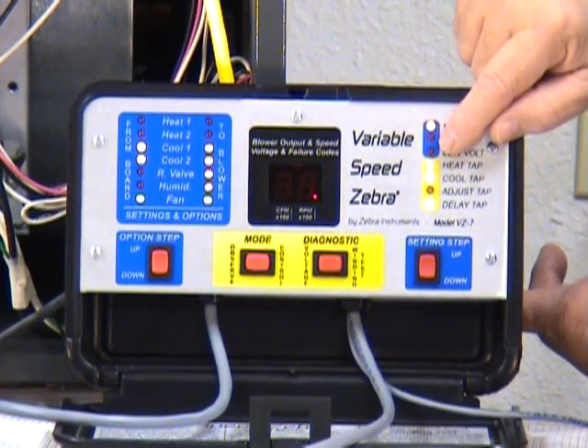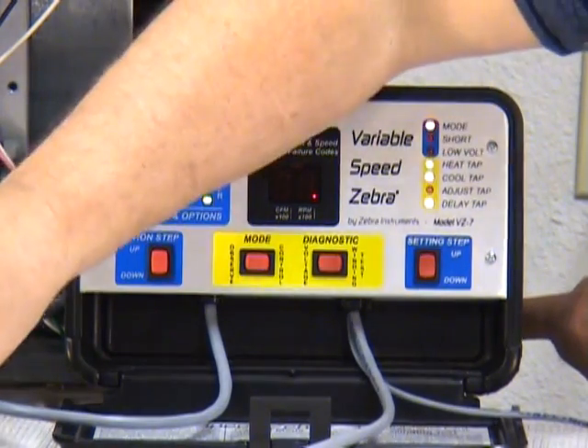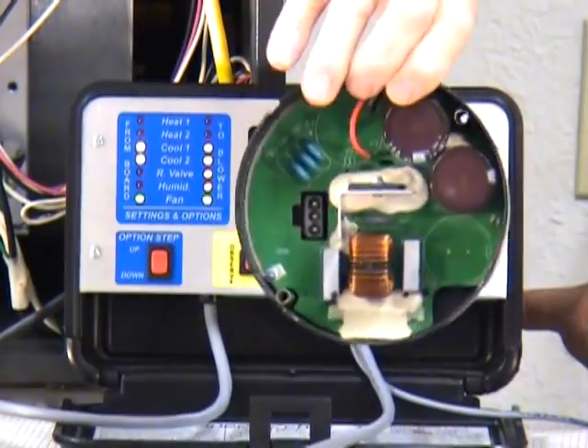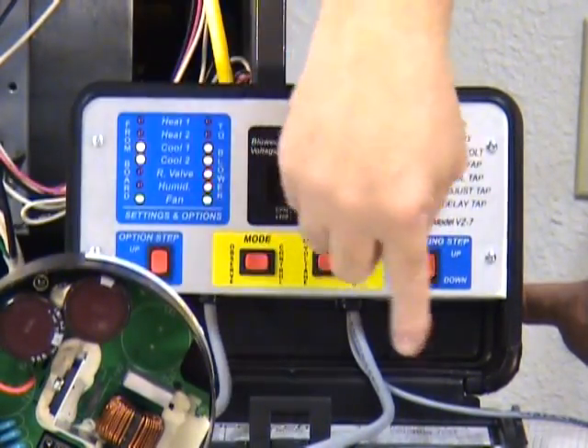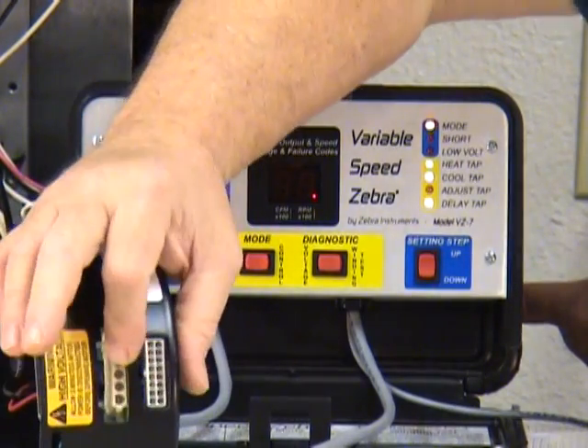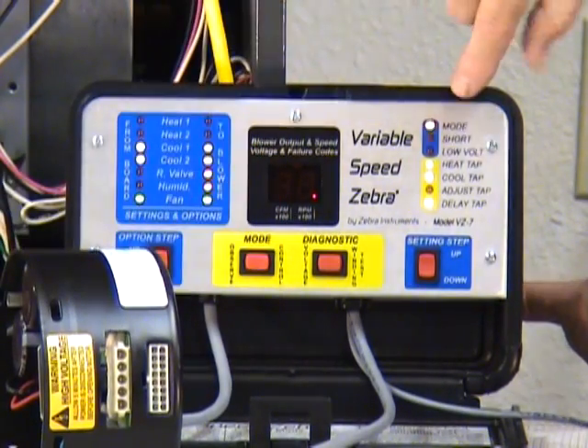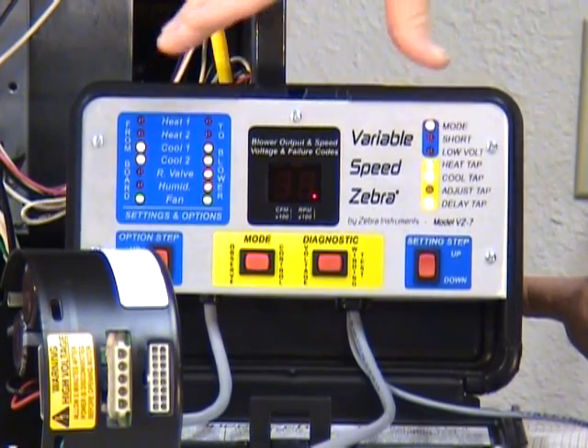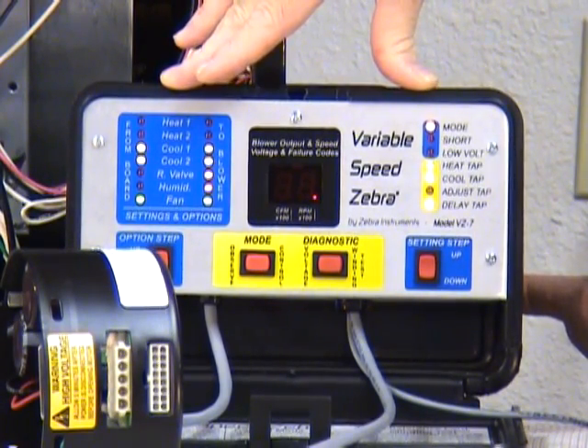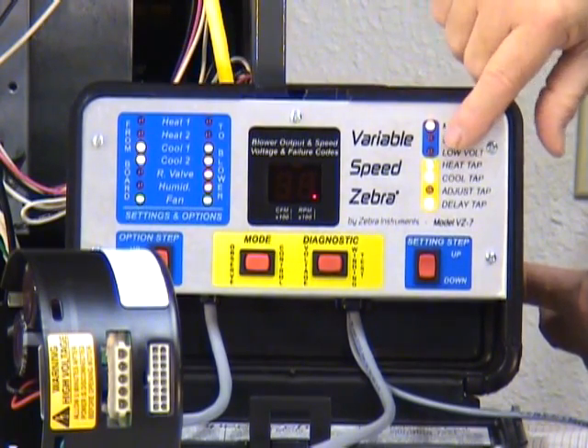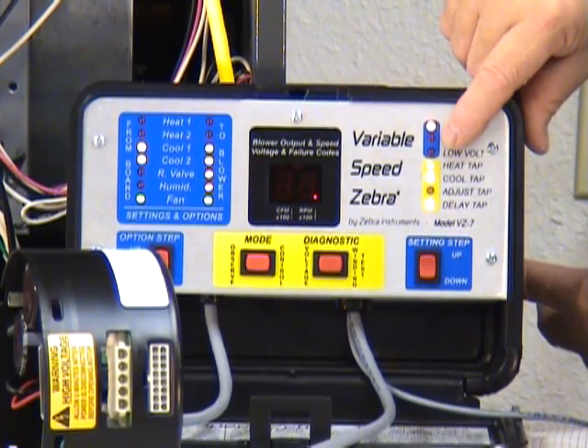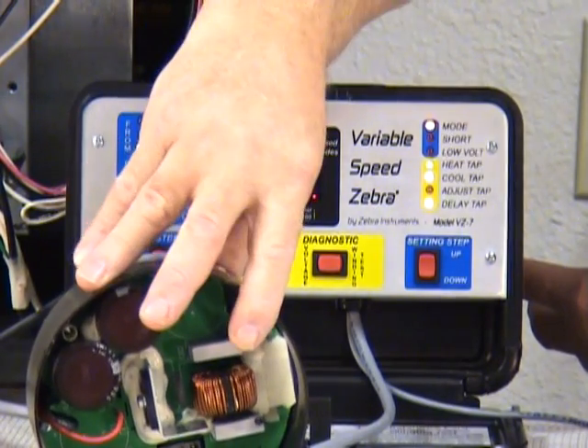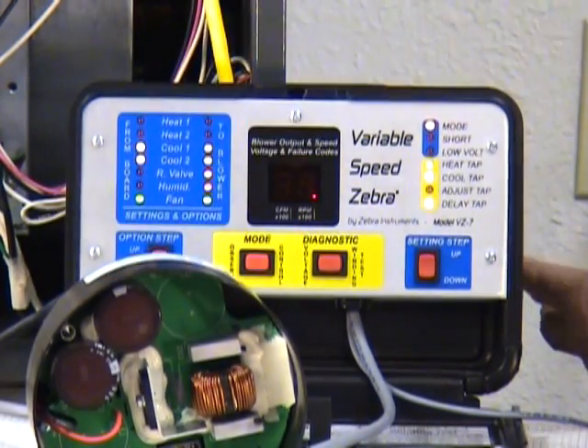The short light would only come on if something inside this electronics package was shorted and you powered up the system and the variable speed zebra, instead of seeing the right signals in here, saw a direct short. That light will come on indicating that a circuit breaker has tripped in the variable speed zebra. It's an automatic resetting circuit breaker so that when you disconnect the power and disconnect the problem and turn it back on, the circuit breaker will reset itself. But it's saying, hey, shut this thing off right away. You got a short in the system. Don't leave it on any longer than necessary. Automatically, at that point, you know you've got a failure in your electronics module.